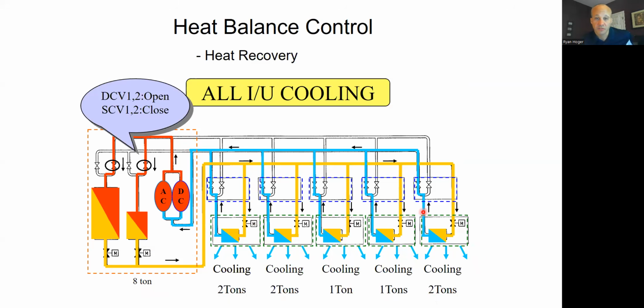If I'm in cooling mode, these guys are all evaporators. These guys are all condensers. My 2 compressors both run max in this case because I need the full 8 tons. They're sending their hot refrigerant to the condenser coils, right? And then those coils are sending the cooler refrigerant to the indoor units to pick up the heat from your space. That's going back into my compressor. It's like every cooling system we've ever talked about, except that my indoor coils are spread into 5 rooms instead of into 1 room, or into 1 duct. Other than that, it works exactly the same.